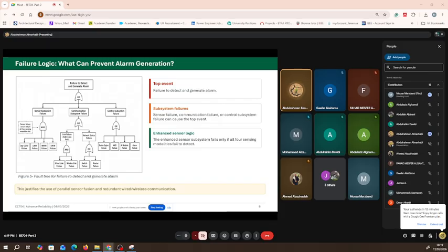For communication, the enhanced system uses wired and wireless links as redundant paths. Therefore, communication is more reliable because one link can support the system if the other link fails. However, switches and routers are still required components.